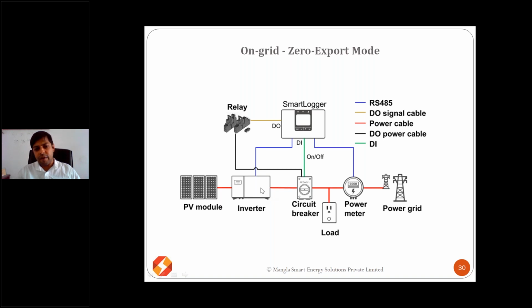If there is any flow coming from the inverter side to the power meter side, if there is any excess power after the load coming to the power meter, then it will send a signal to the smart logger, whereas the smart logger will try to give information to the inverter and commands to reduce its production if it is excess. In case that is not the case, if it crosses beyond a particular limit, then the relay will be switched on and the circuit breaker will apply and the solar plant will disengage if the inverter is not able to control its power production.